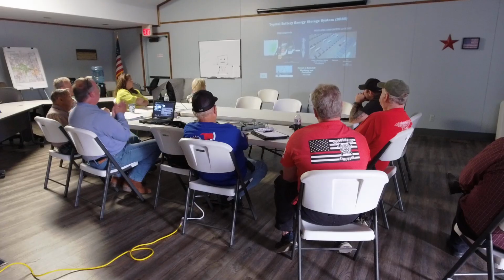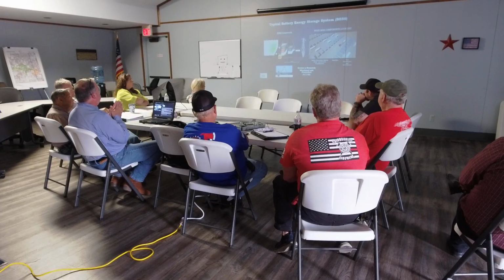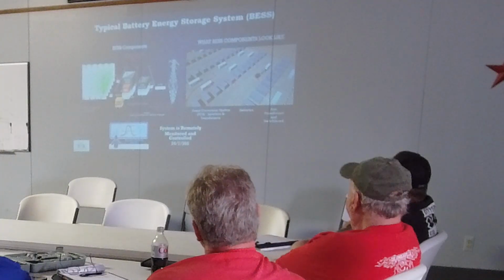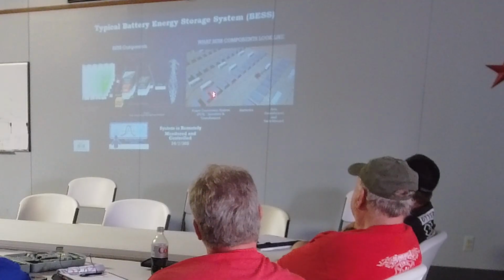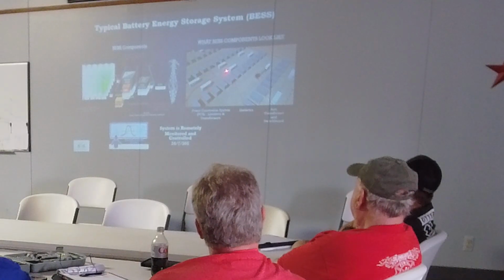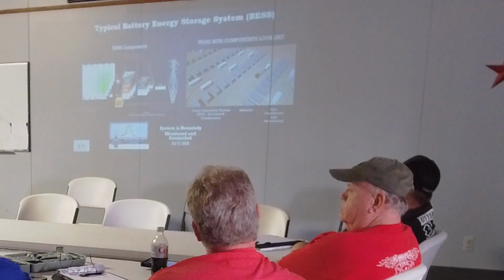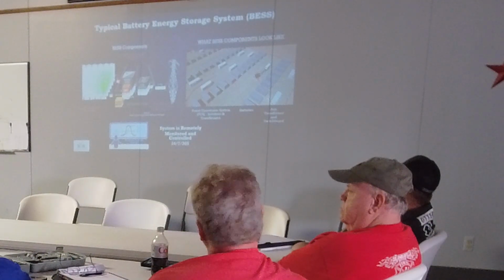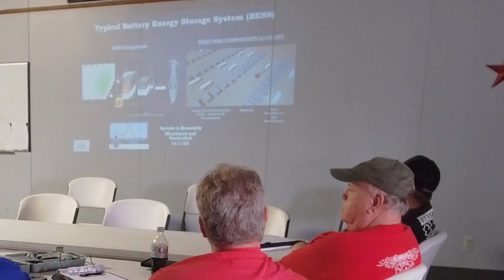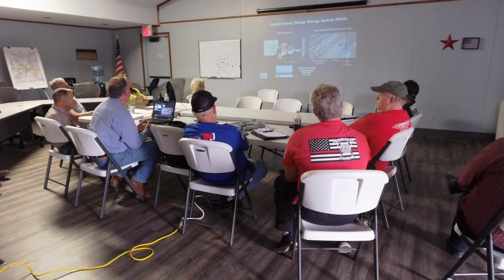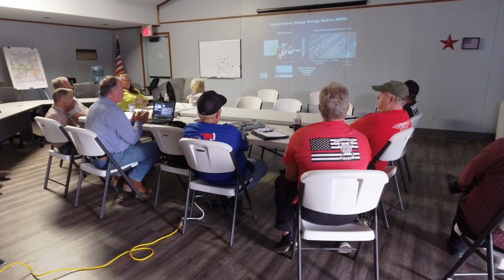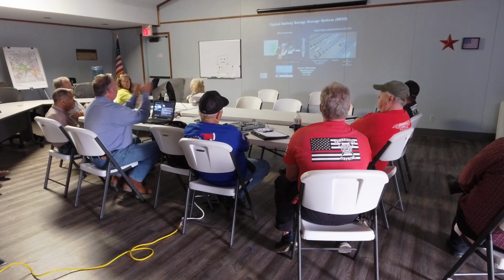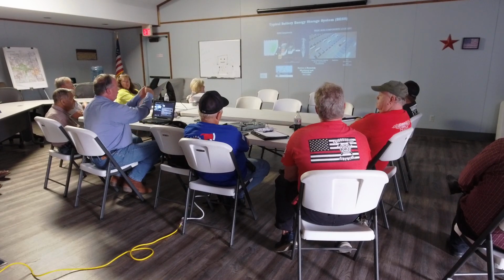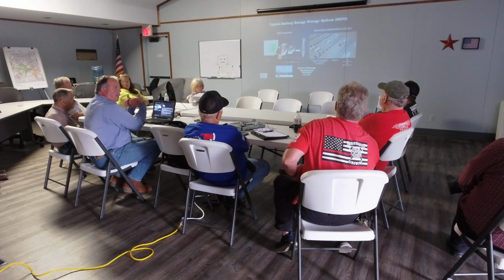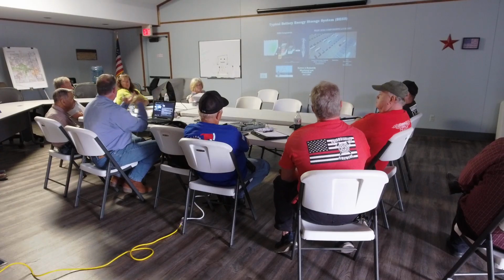This is what a typical battery yard might look like. The darker gray containers are the actual battery containers, and the lighter gray are the inverters. One inverter is responsible for 3 to 4 battery containers. The most common configuration we're seeing today is called a quad, with 2 containers side by side facing one way, and 2 more behind them facing the opposite way, so the doors all line up correctly.